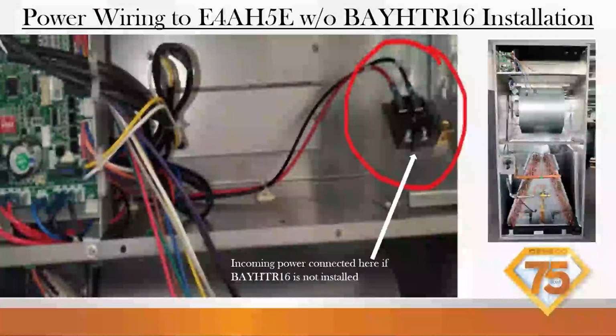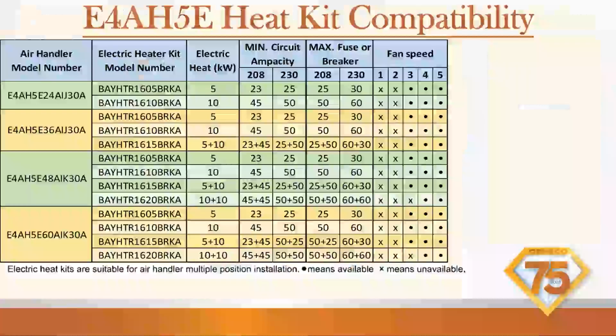This is without heat strip. I'll show you with the heat strip here in a little bit. Pretty easy to land. So you've got your L1, L2 line voltage incoming. We're going to enter incoming power connected here. If the heater is not installed, we'll go over what to do with those wires when heat strips are installed here in a second.